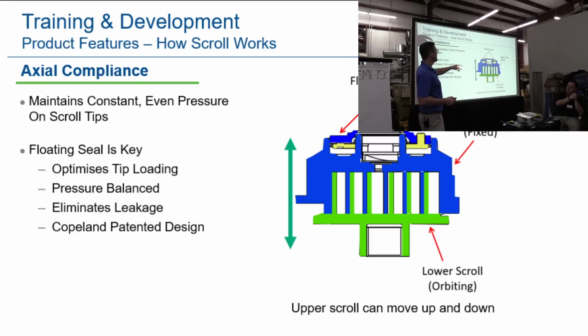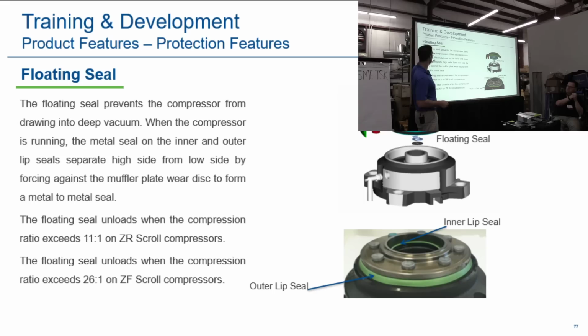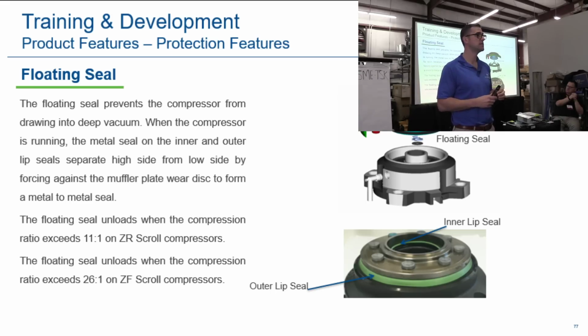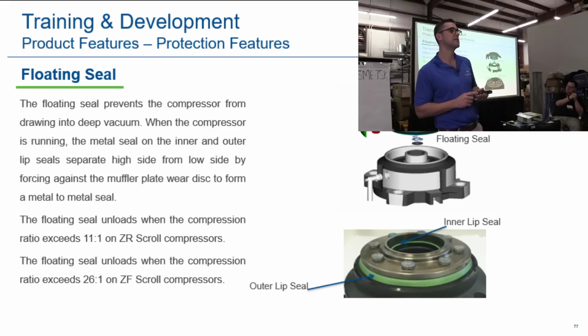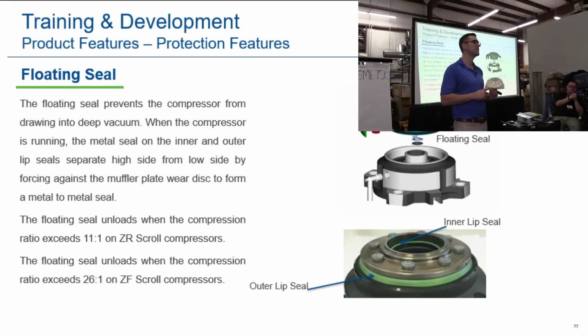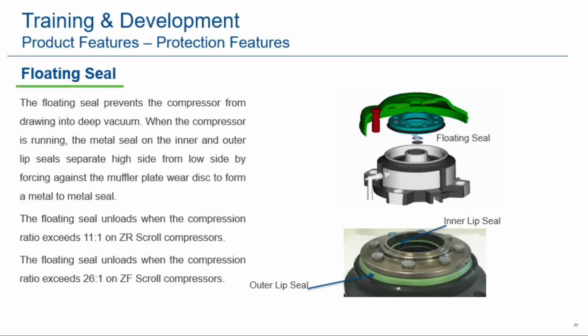One of our key designs for our scrolls is something called a floating seal, optimized tip load. The best way to show this is that the floating seal prevents the compressor from drawing into a deep vacuum. That's really important. Should you run any compressor in a vacuum? No. What could happen? I heard something about the windings burning up. Yeah, you could get an arc inside there and it shorts out the windings. That's why you never power a compressor that's under a deep vac before you charge it up.